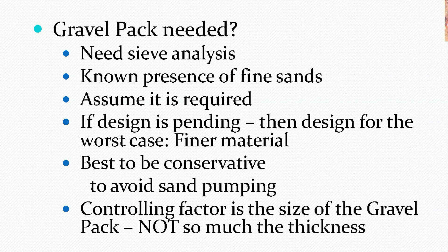It's best to be conservative and avoid sand pumping. The controlling factor is the size of the gravel, not so much the thickness. Again, if somebody comes in with three-quarter inch gravel there's no way sand will stay out. Also watch the thickness — the borehole should be larger than the casing or screen so the driller can pour in the gravel pack. You need at least two and a half inches, and preferably three or four inches — four inches is a good thickness for the gravel pack.